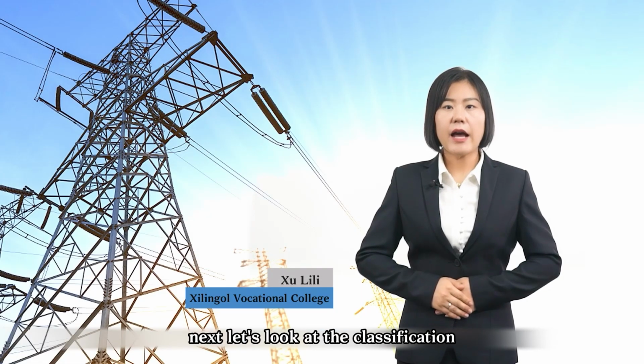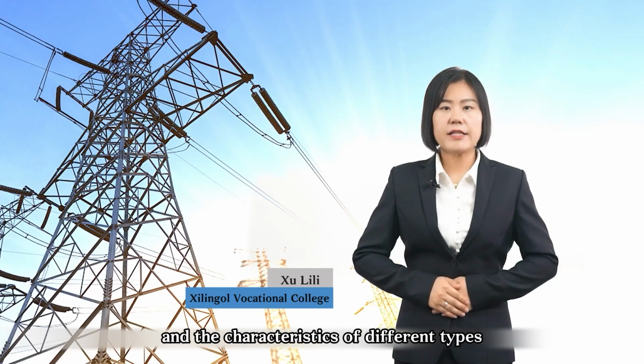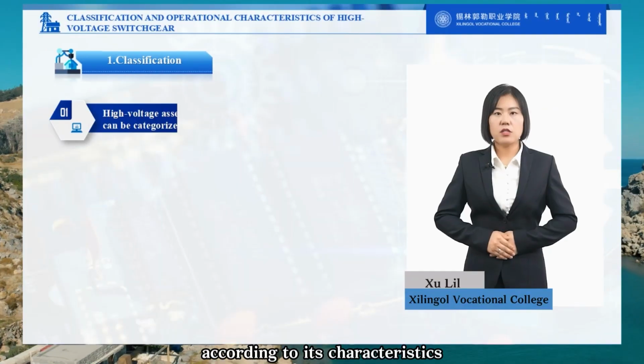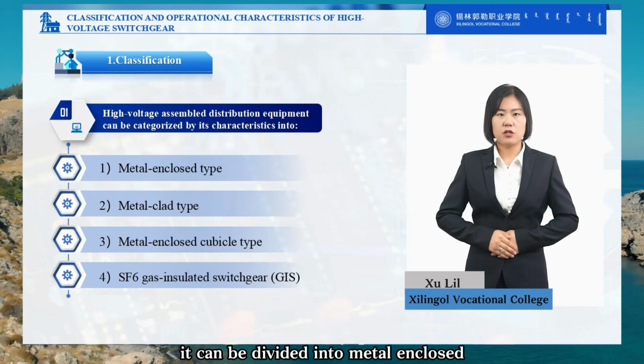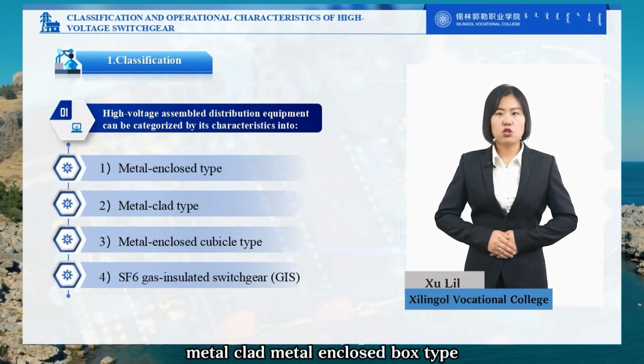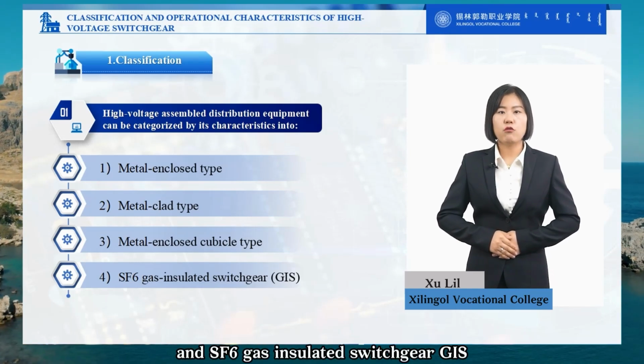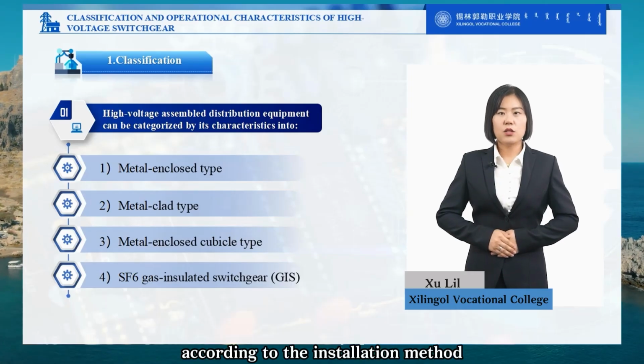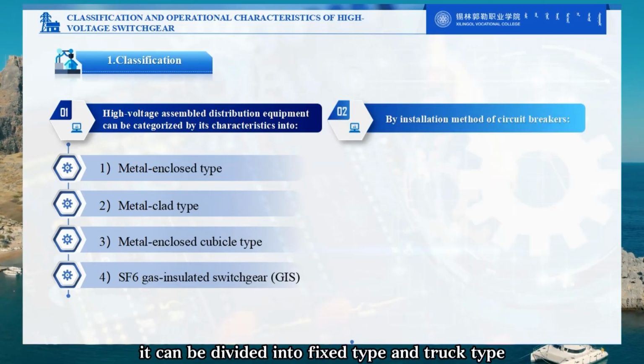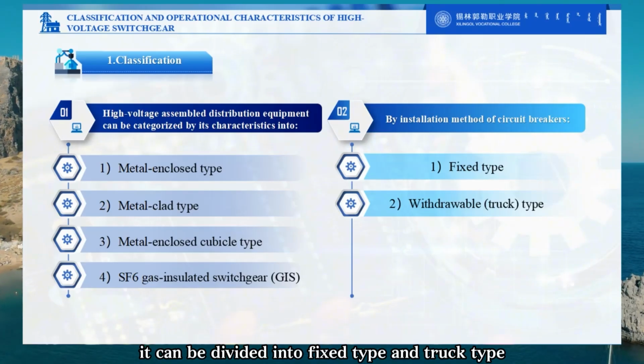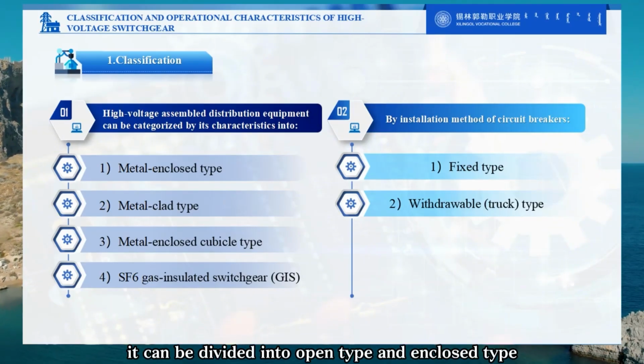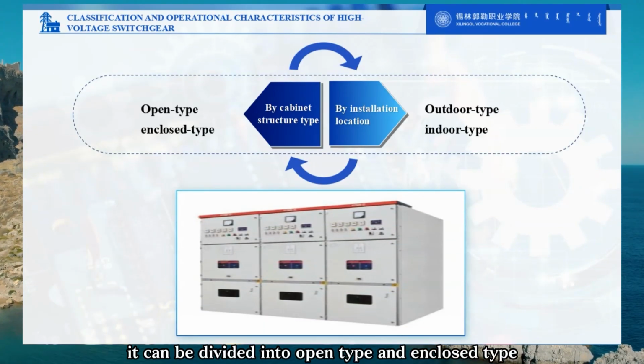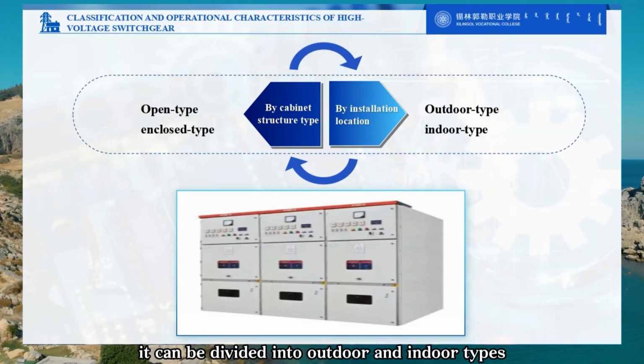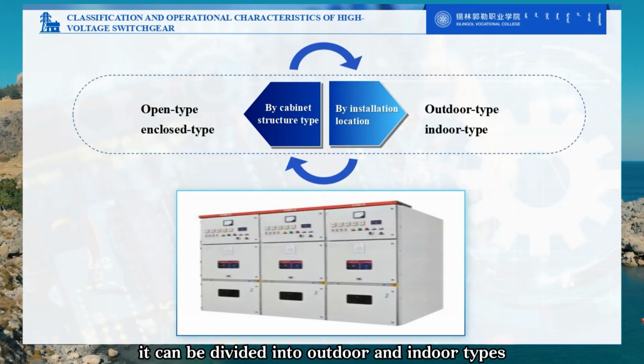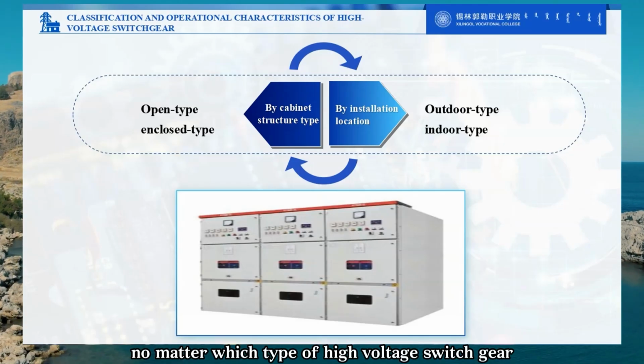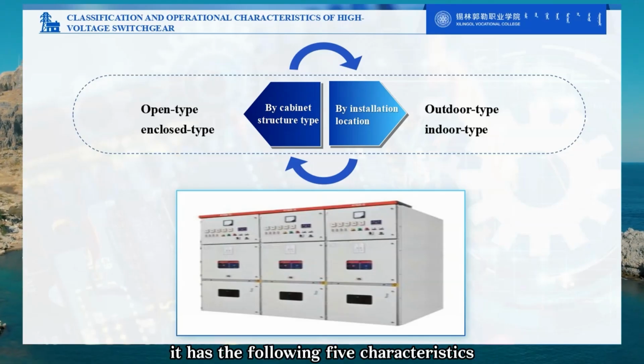Next, let's look at the classification of high-voltage switchgear and the characteristics of different types. According to its characteristics, it can be divided into metal-enclosed, metal-clad, metal-enclosed box type, and SF6 gas-insulated switchgear, GIS. According to the installation method of the circuit breaker, it can be divided into fixed type and truck type. According to the cabinet structure, it can be divided into open type and enclosed type. According to the installation location, it can be divided into outdoor and indoor types. No matter which type of high-voltage switchgear, during operation, it has the following 5 characteristics.